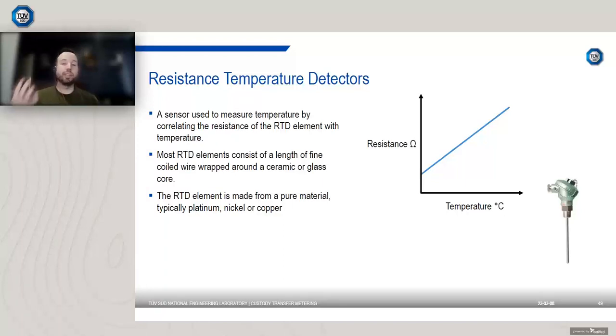Now these come in different wiring configurations. You get 2-wire, 3-wire, 4-wire devices. I won't go into the details, but 4-wire typically is the best choice because it eliminates the resistance of the measuring lead. So if you think, you've obviously got 4 wires that are required to measure the resistance. If you're using a 2-wire system, for example, and you have a particularly long length of cable, by the time it gets to your control device, the resistance that you're going to measure includes that cable length. Now that can be quite significant, but with a 4-wire system that's eliminated. So 4 wires is usually the best choice.